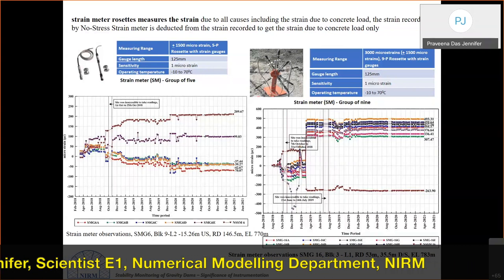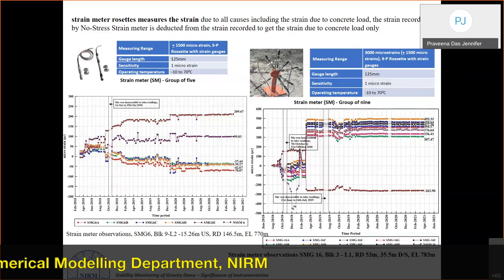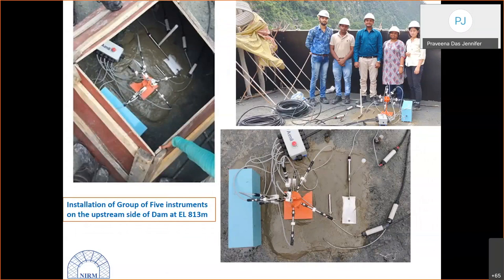At PHPA II, a group of nine strain meters is used at most levels, particularly at blocks 11 and 3. A typical installation combines a group of strain meters with a stress meter, a no-stress strain meter, a piezometer, and a temperature meter — five instruments co-located at one point. This co-location enables correlation studies between temperature, pore pressure, stress, and strain at a single joint.